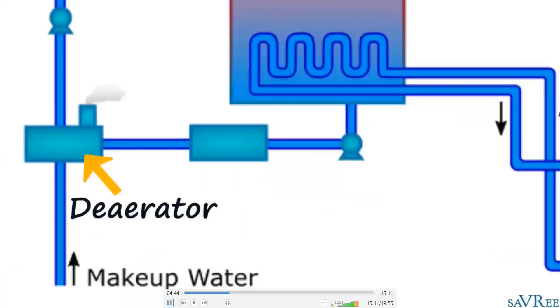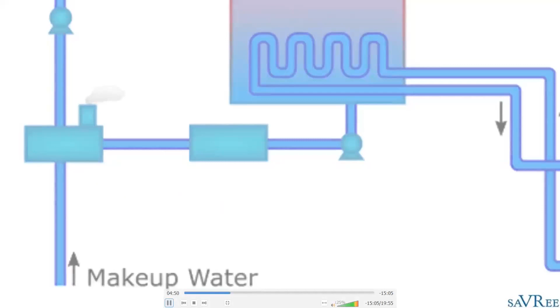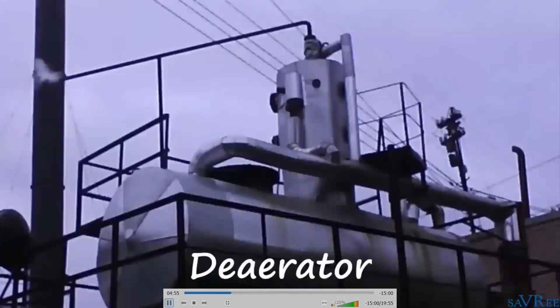So this make-up water has to be treated chemically and mechanically, and we do that quite often in a deaerator. The deaerator is going to reduce the oxygen content. You can see a deaerator here. It looks something like this, a big drum. Basically it's a heat exchanger. It also reduces the CO2 content of the water. And before the water gets to the deaerator, it's going to be filtered, etc., to take out those particles that might be floating around in the water.